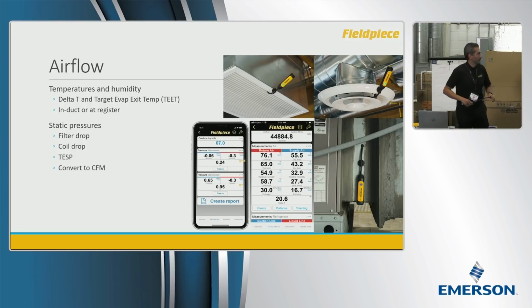Now, it's a very simple measurement to do. Let's talk about delta T and target evaporator exit temperature. You have two psychrometers, one set at the return and one set at the supply. The psychrometers have switches on the back that are labeled return and supply, and you have a color indicator, red or blue, indicating which one you're at. That way the app knows exactly where to put the measurement based on how you set these up. They're both interchangeable. They don't have to be on one side. So if I'm going to go in duct, I could probably use this for that. There's no hose. All right, let's just go register grill.